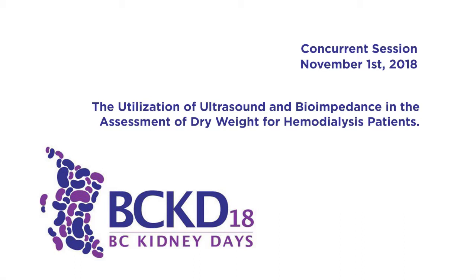So I thought we'd talk about some other tools that you probably are familiar with. One that's commonly looked at is blood volume monitoring, or relative plasma volume monitoring, which uses optical transmission to measure an intradialytic change in hematocrit. So this is in real time. You can see it on the machine, and you can see a slope, which is a function of both the ultrafiltration rate and the ability of the patient to refill. And that may be reflective of their volume status, or it may reflect that they can't refill.